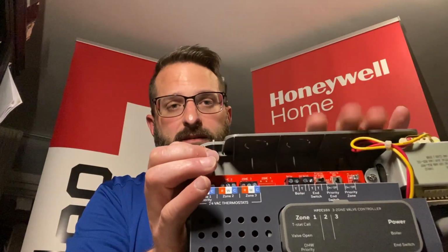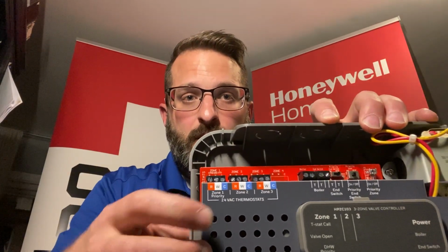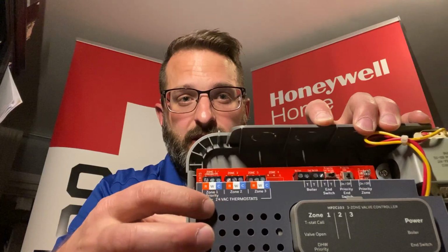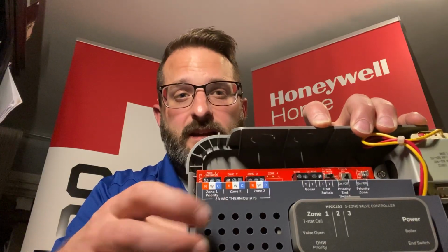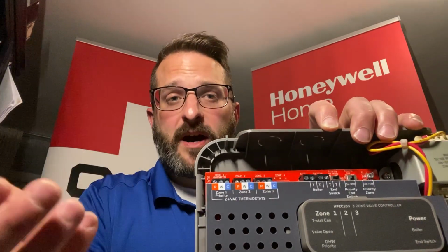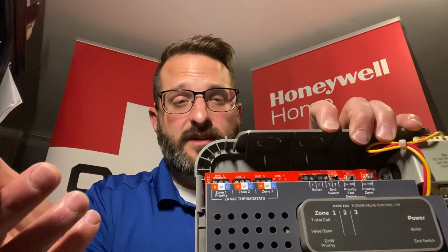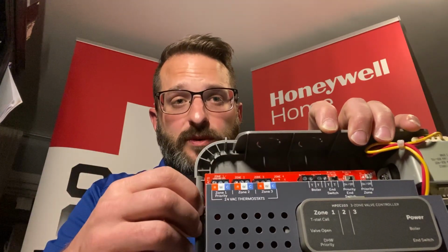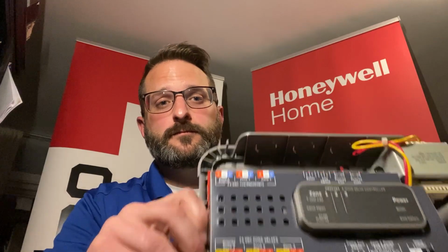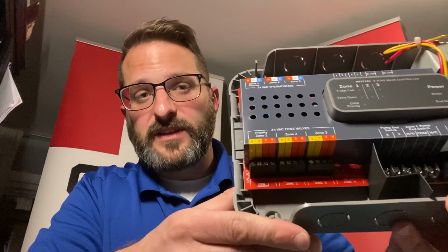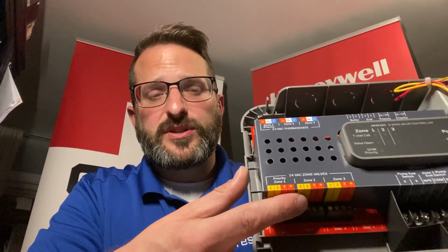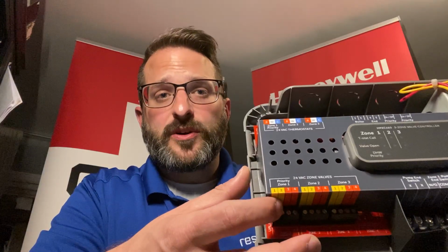So looking at the inside, we color coded the thermostat side of things, and then we added a dedicated common leg to support power stealing and Wi-Fi thermostats. So we have a constant 24 volts going there. Moving down on the zone valve side of things, we called out the end switch and the power, but we also support, power stealing, or not power stealing, I'm sorry, 3-wire zone valves if need be.